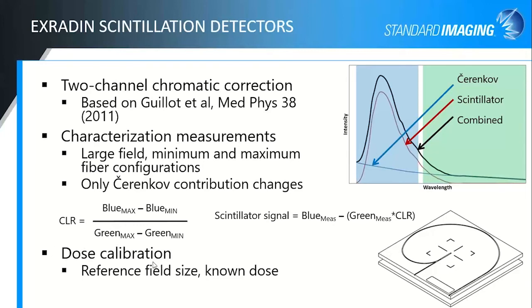If you want to do a dose calibration of this detector, that really is just a scaling factor that's inserted in here. So you can do a dose calibration with a reference field size, give it a known dose, and then you can get your scintillation measurement output in terms of dose.